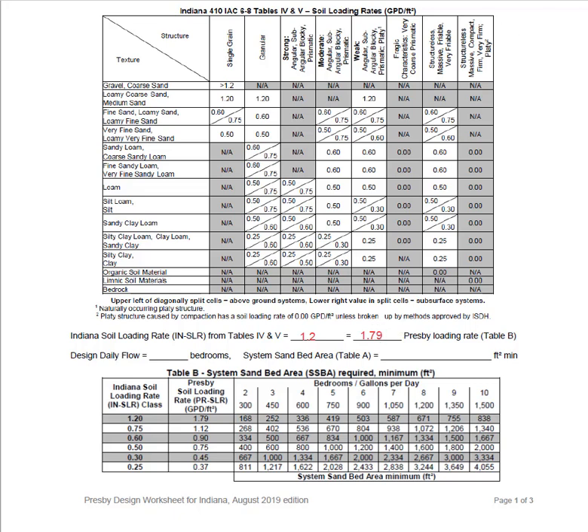Now we can finish determining how much sand bed area is needed for our system. We will start at the 1.79 loading rate and move to the right until we are intersecting the column for four bedrooms. The value at this intersection is our minimum sand bed area. In this case we will need at least 336 square feet of system sand bed area.